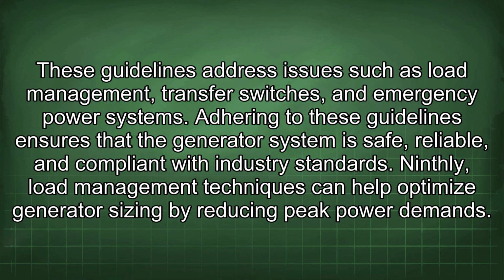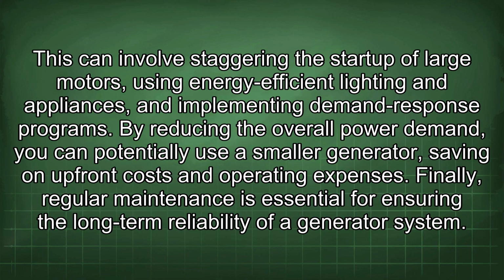Ninthly, load management techniques can help optimize generator sizing by reducing peak power demand. This can involve staggering the startup of large motors, using energy-efficient lighting and appliances, and implementing demand response programs. By reducing the overall power demand, you can potentially use a smaller generator, saving on upfront costs and operating expenses.